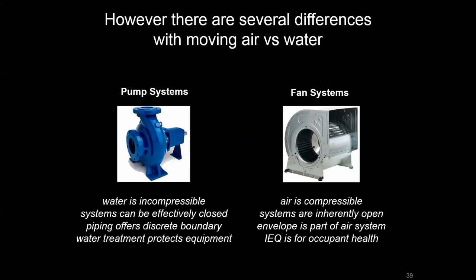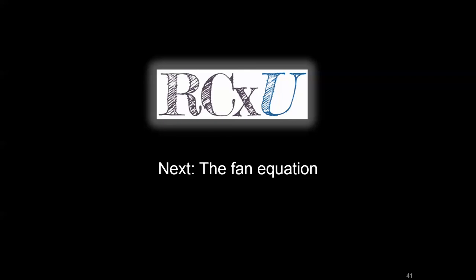With pumps, you may send treated water through the system to protect equipment. With fans, air filters protect equipment but indoor environmental air quality must also be contended with. With pumping systems, there are only a few configurations commonly seen in the field — primary-secondary and variable volume systems. With airside systems, however, there are many classifications based on how distribution is set up, where the air handling unit is located, and the different approaches it can take. We'll get into how to classify airside systems, but first we'll delve into the fan equation to quantify the fan energy used.